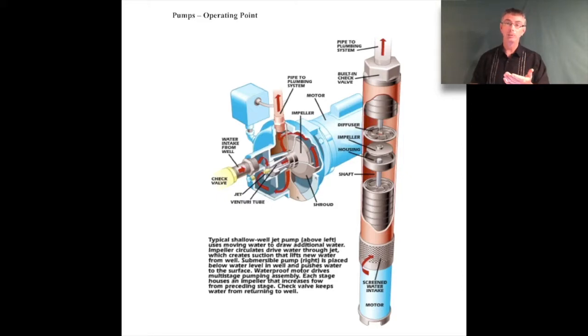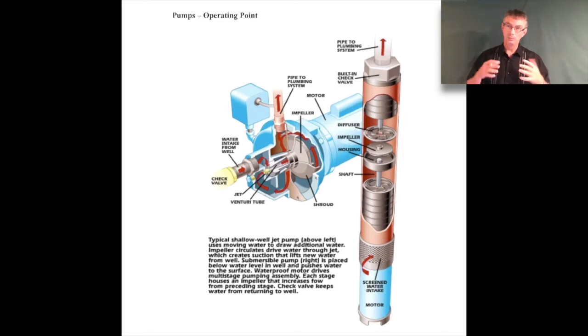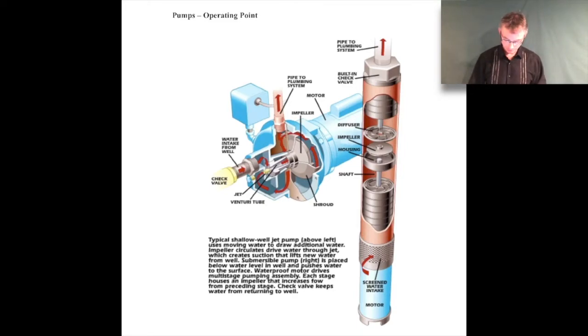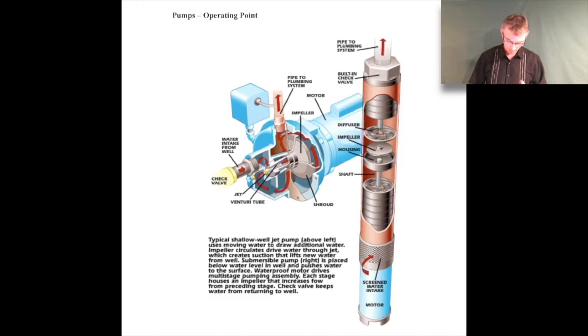The reason for placing the pump at the bottom is that if it's a deep well, as we know from the NPSH lecture, you have to have the pump down as far as you can to avoid cavitation. So this kind of pump is designed to be dropped into the well casing. You can see the motor here that's designed to turn the pump, and you have a screen for the water intake so the water comes in through there - the screen just helps prevent debris from being collected.